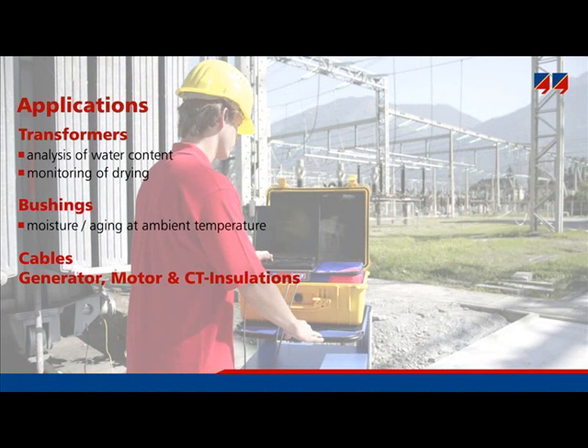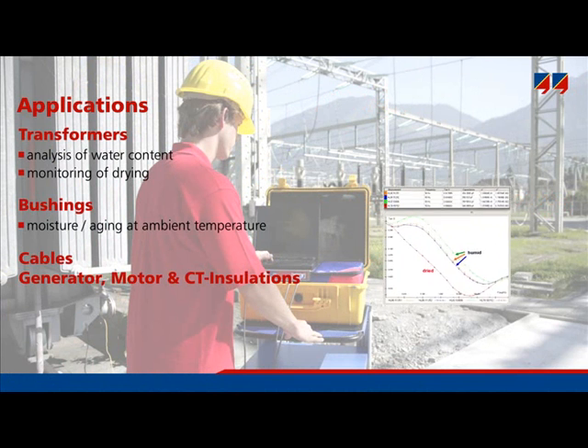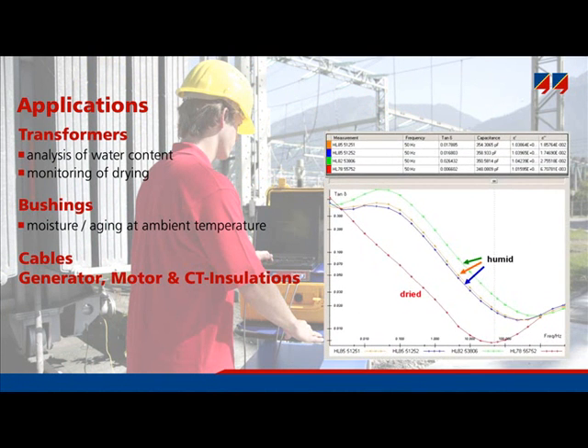The diagram shows how moisture affects the dissipation factor of resin impregnated paper bushings. Its value was initially measured in the factory and is largely dependent on the environment in which the bushings are stored. The dissipation factor will be high for humid conditions or low if the air is dry.